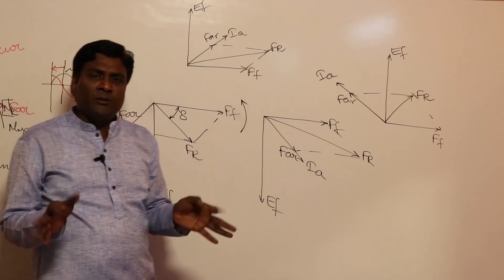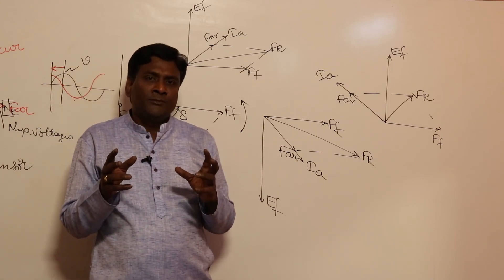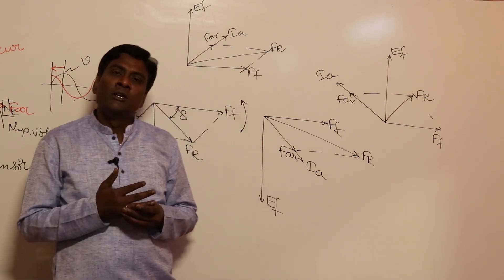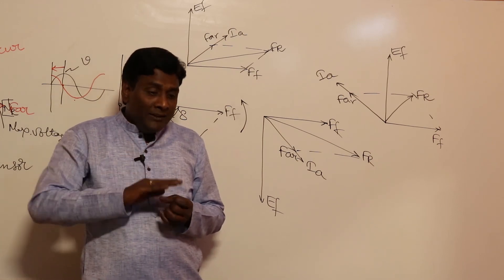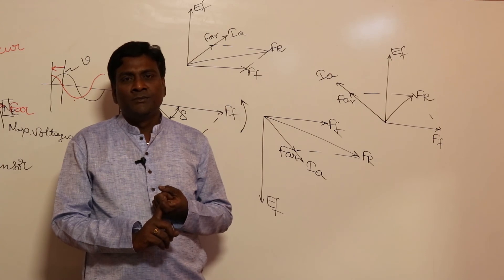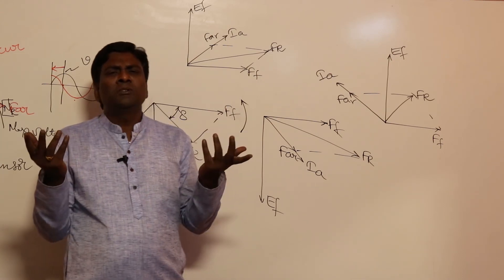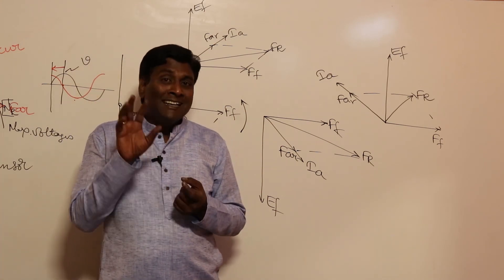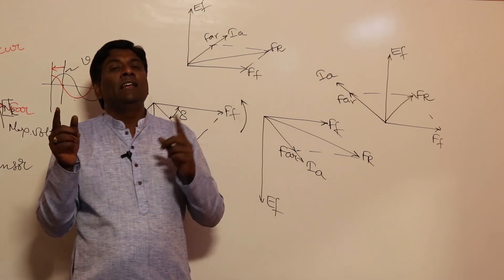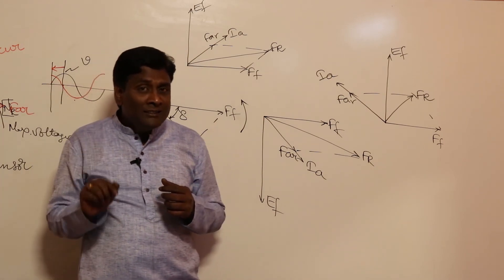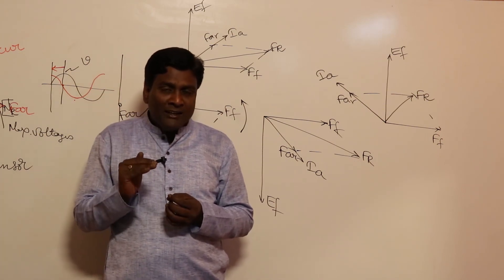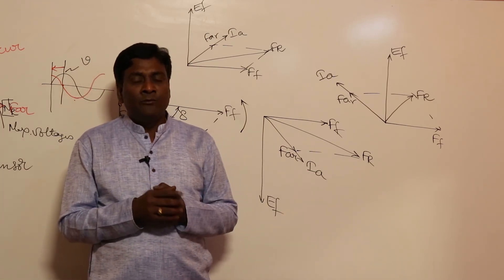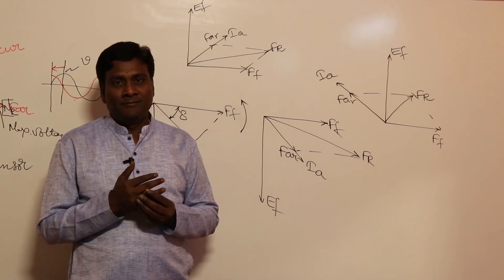Conclusion is very simple. Please repeat the video multiple times if confused, because this is not a physical concept that's easy to visualize. Once we start phasor diagrams and problem solving it will become simple. Final conclusion: synchronous machine when over-excited delivers reactive power with demagnetizing armature reaction effects — increase field current. When under-excited, the synchronous machine absorbs reactive power — reduce field current.